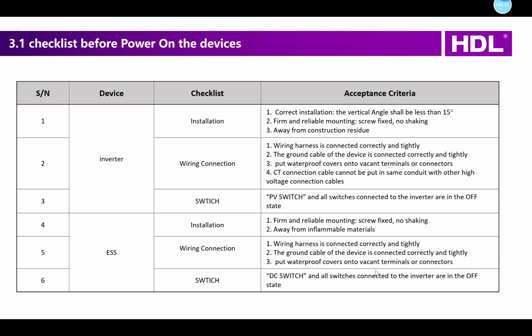The first one is for installation. The vertical angle shall be less than 15° because you mount the inverter on the wall, but if you don't fix it properly and it has some movement, this will also affect the function and the use of the inverter itself. And also, screws fixed, no shaking. This is basic. And also keep it away from construction residues. And especially for the connection, you need to make sure the wiring harness is connected correctly and tightly. You need to check it. And also the ground point wiring is connected correctly.